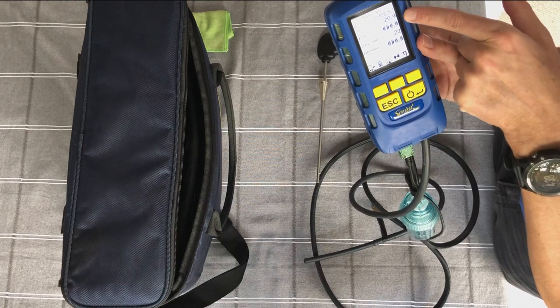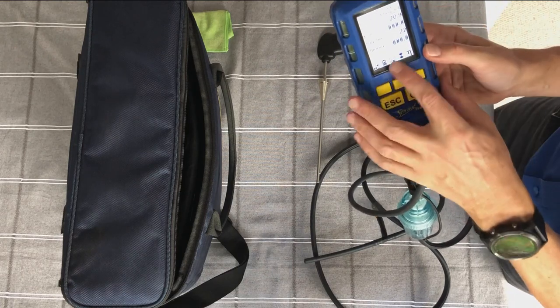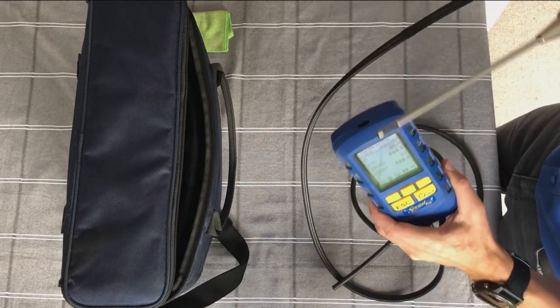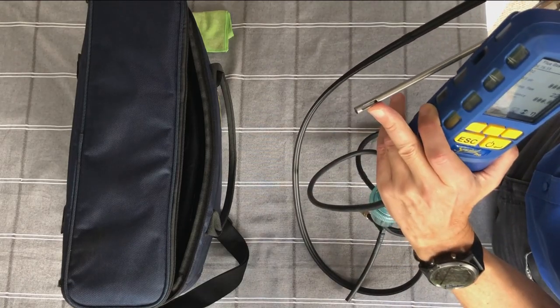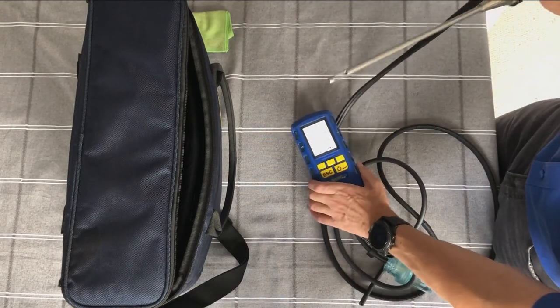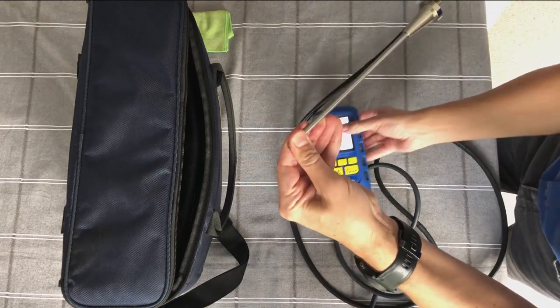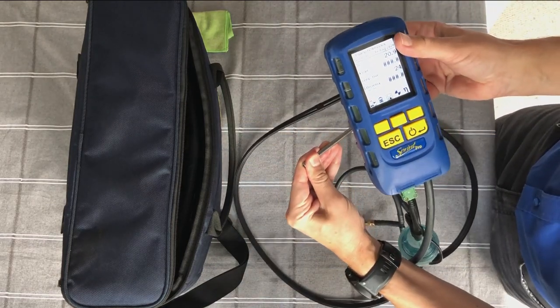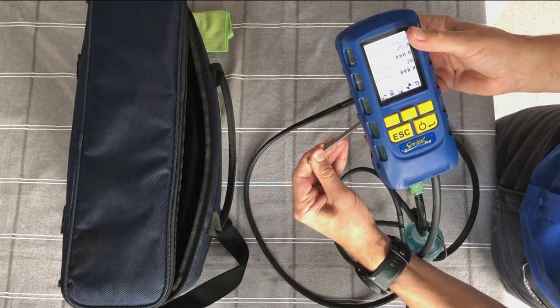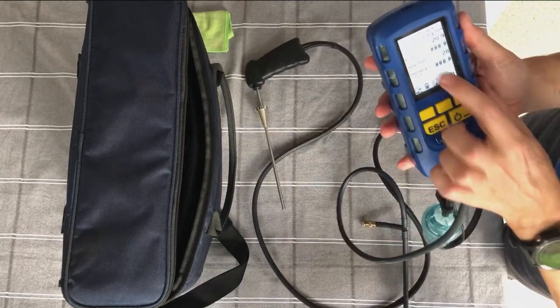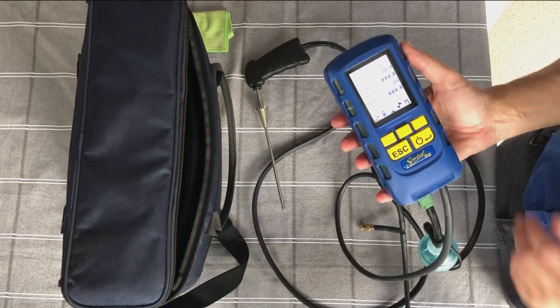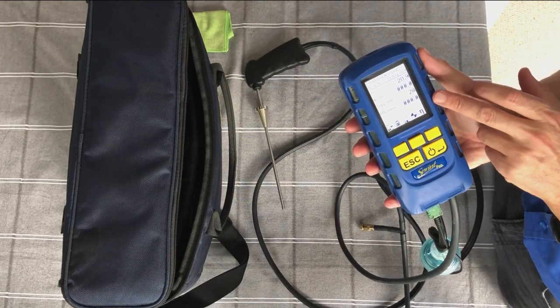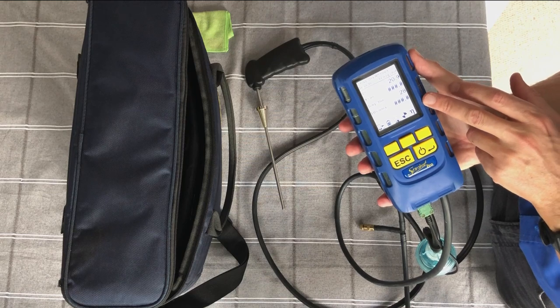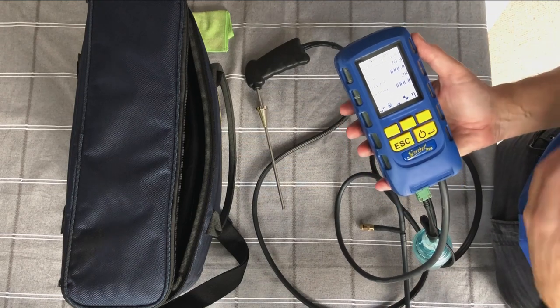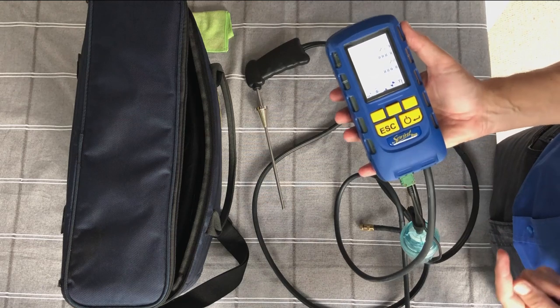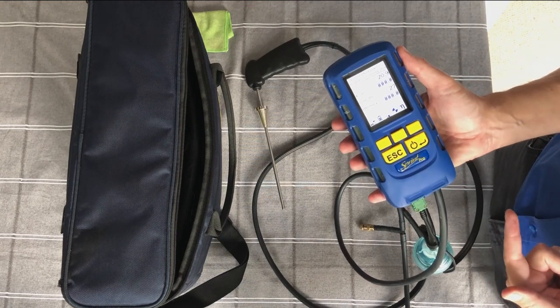So the next page I've got the O2 again, excess air, the flue temperature, and the efficiency. In the tip here of the flue probe, I've obviously got a thermocouple. So if I warm that a bit with my fingers, there you go, you see the flue temperature starting to rise as I warm it up to body temperature. The efficiency on this is different as well. It will automatically know if it's a high efficiency boiler or a standard efficiency boiler from the flue temperatures and the flue gas readings. So the calculations are slightly different, whether it's a high efficiency or a standard efficiency appliance.